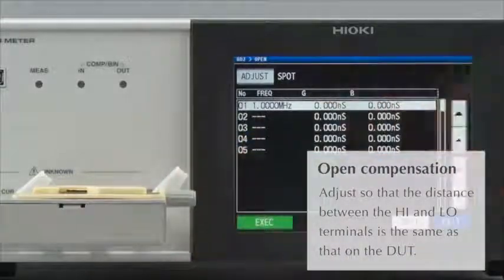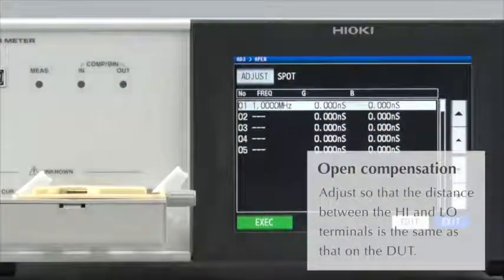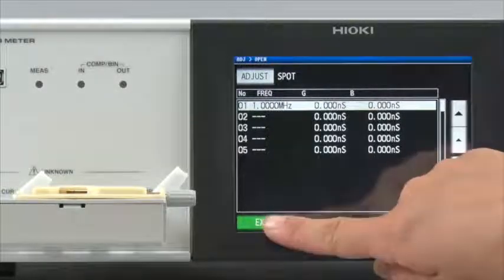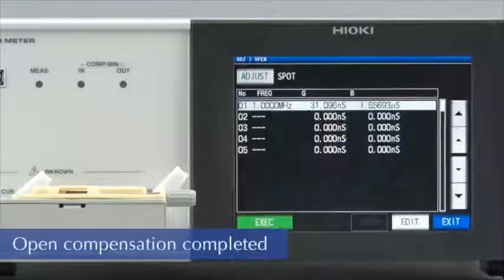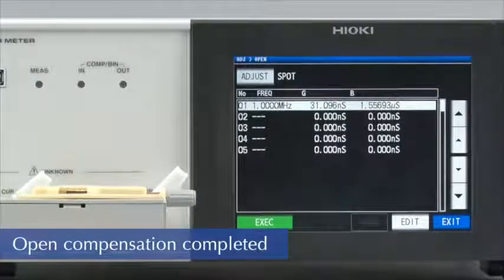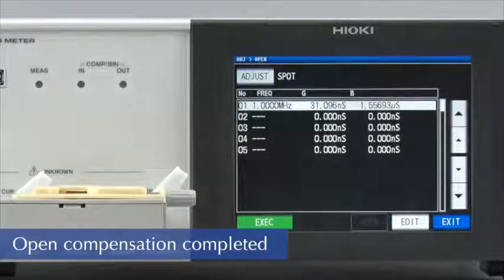Now, remove the DUT. By doing this, you will be conducting open compensation with the electrodes spaced at exactly the same distance as that on the DUT. This completes open compensation at 1 MHz.